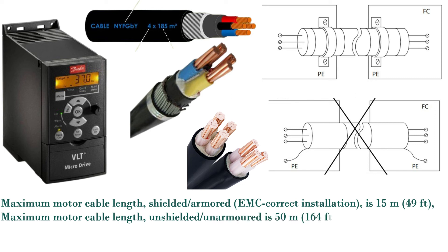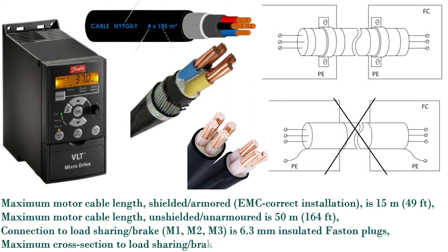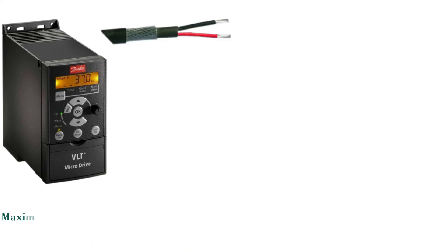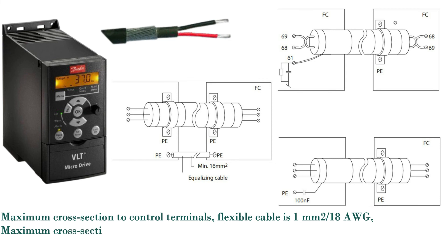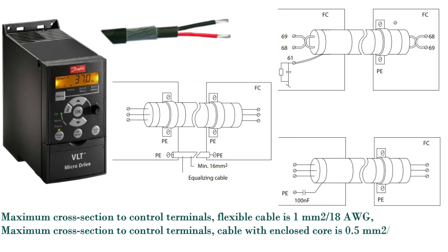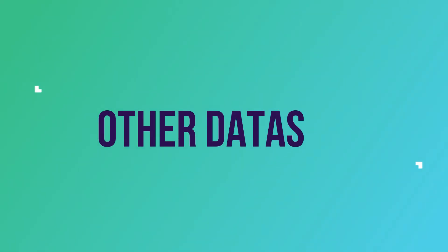Connection to load sharing/brake M1, M2, M3 is 6.3 mm insulated fast-on plugs. Maximum cross section to load sharing/brake M4, M5 is 16 mm² / 6 AWG. Maximum cross section to control terminals, flexible cable is 1 mm² / 18 AWG. Maximum cross section to control terminals, cable with enclosed core is 0.5 mm² / 20 AWG. Minimum cross section to control terminals is 0.25 mm² / 24 AWG.